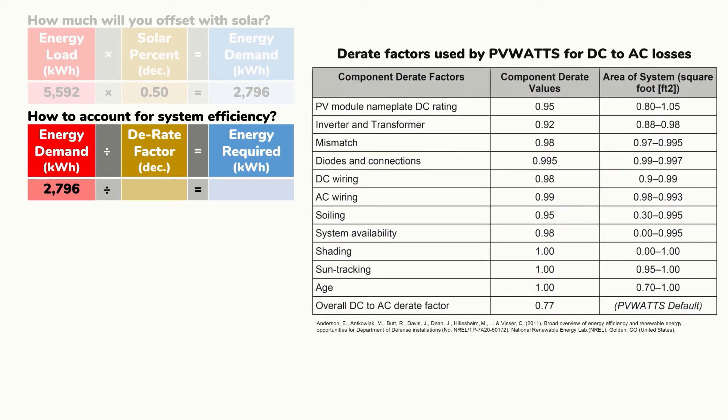Now we'll divide this revised energy value by a derate factor that accounts for the efficiency of the entire electric system. Derate factors account for losses from voltage drop within DC or AC wiring, shading on the panels, or dust and bird droppings blocking sunlight. To account for these losses we'll use a derate factor of 0.77, in accordance with models used by the National Renewable Energy Lab. Dividing by 0.77 gives us a resulting value of 3,631 kWh — the energy needed to provide 50% of our electrical needs.